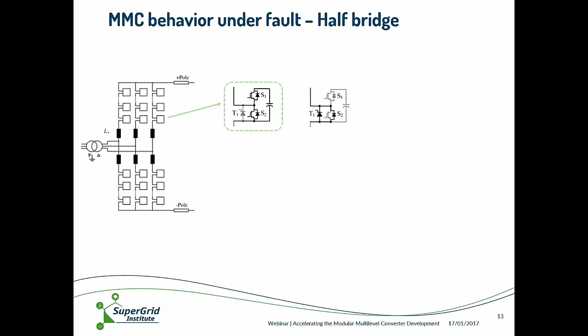All that to say that for the creation and validation of protection strategies for MTDC grids, it is mandatory that the behavior of the MMC under fault is properly modeled and simulated. Now let me show a few examples of the setups based on OPAL-RT systems that we use.